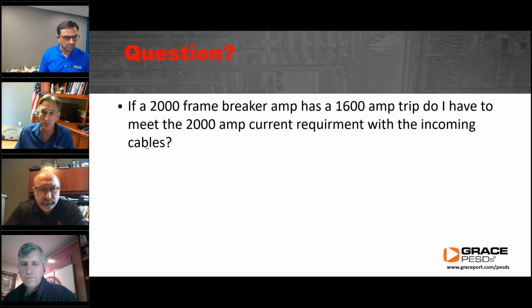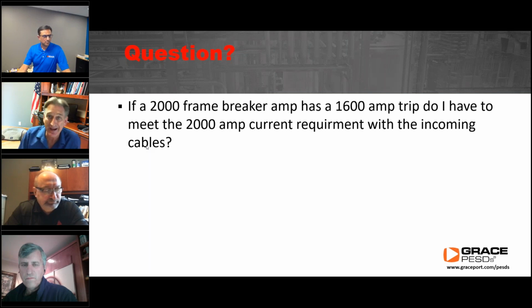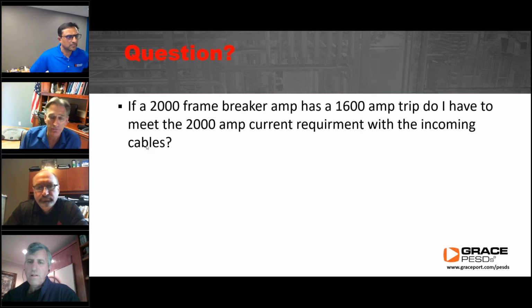qualified persons. So if this frame breaker is in an electrical equipment room and the electrical equipment room is in a room that is behind locked doors, and this room is only accessible to qualified persons, then the conductors coming out of that would only have to be rated 1600 amps and not 2000. So 240.6 B and C is where you want to look for the information for this answer.